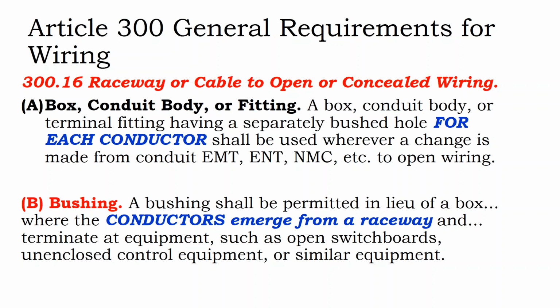So we have: a box, conduit body, or terminal fitting should have a separately bushed hole for each conductor, and shall be used whenever there's a change from conduit to open wiring. So that's kind of interesting, because your amateur installers will just take conduit and shove as many wires into it as they can. But what we're seeing is there actually should be a hole for each conductor going in there. And that's where you see these caps that go into your conduit that can support and separate each different conductor. A bushing shall be permitted in lieu of a box where the conductors emerge from a raceway and terminate at equipment such as open switchboards or similar equipment. So there are exceptions to the rules.